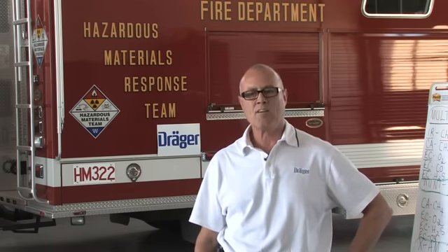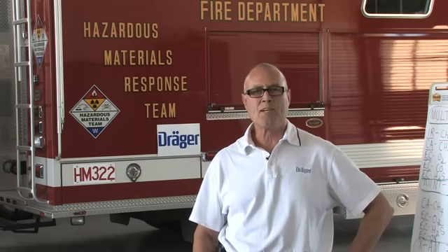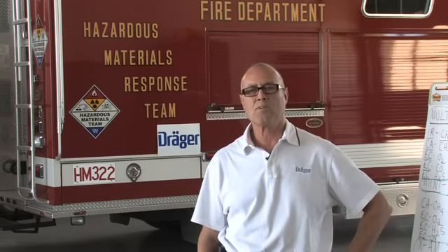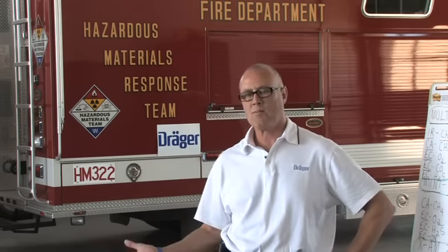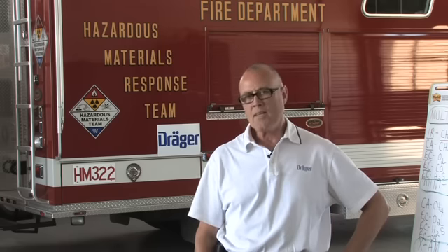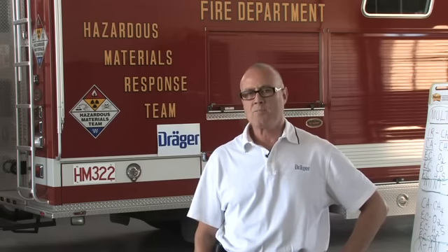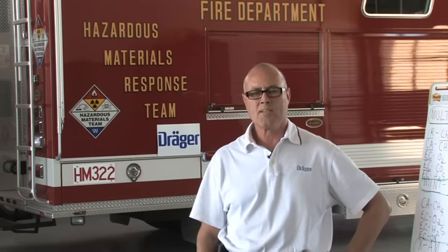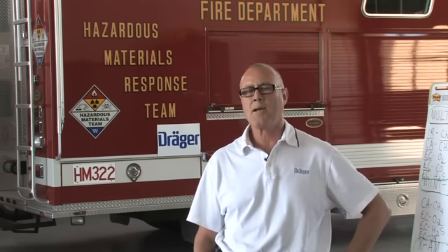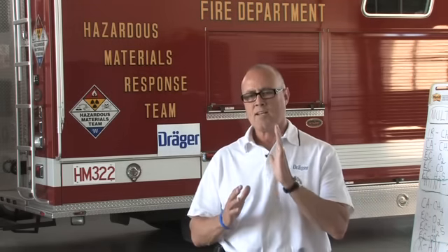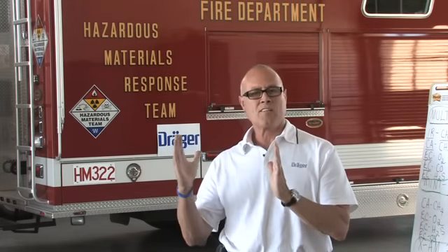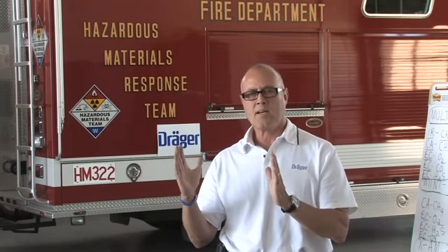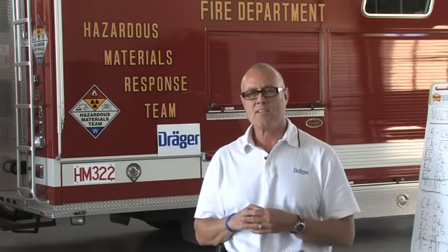Oxygen obviously is there to make sure you have plenty to breathe, and there's alarm thresholds to protect you so you can get to a fresh air environment. On the combustible detector, that is to protect you from explosions and an explosive environment. It is not necessarily there to pick up minute traces of combustibles, but more to monitor in the fresh air up to the explosion range of a combustible gas. And that's the intent of the gas monitor.